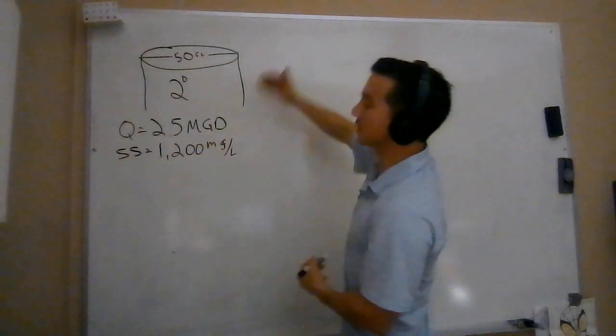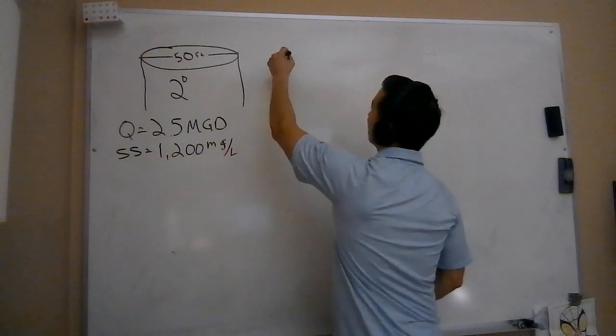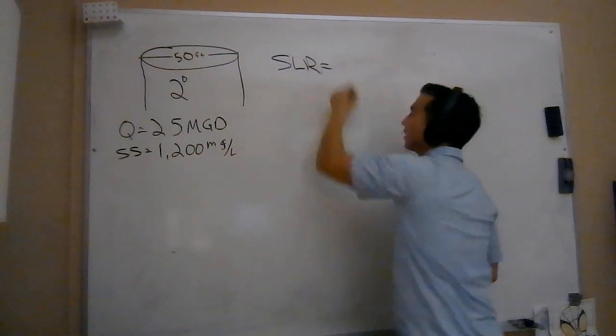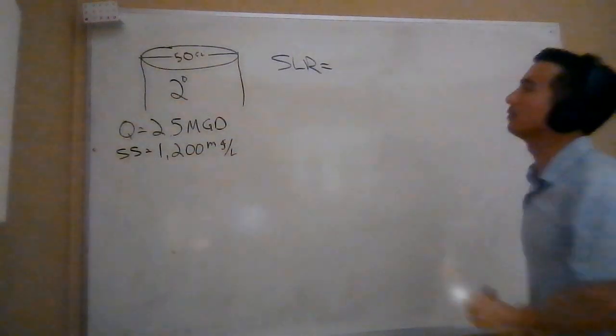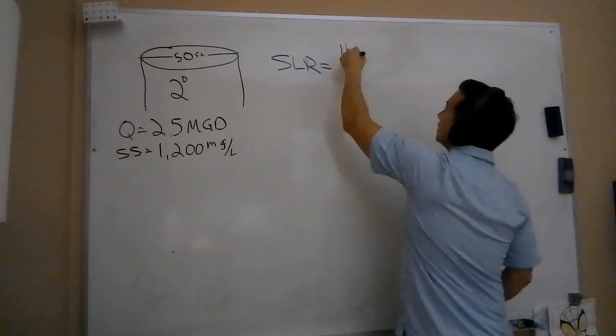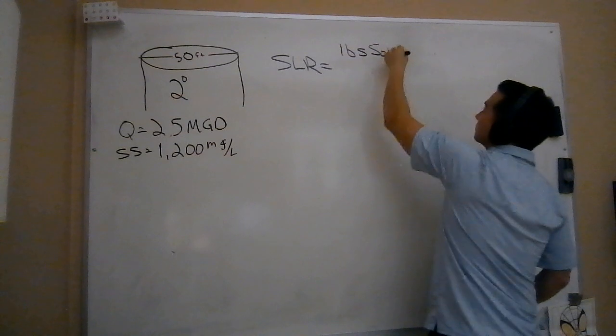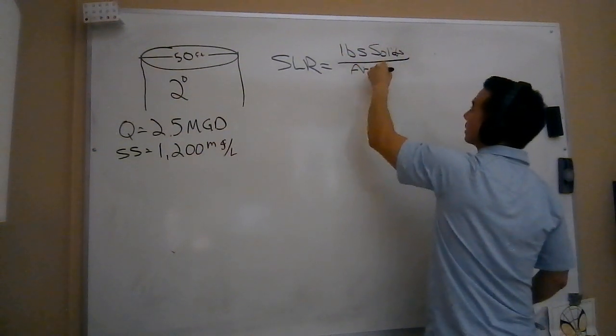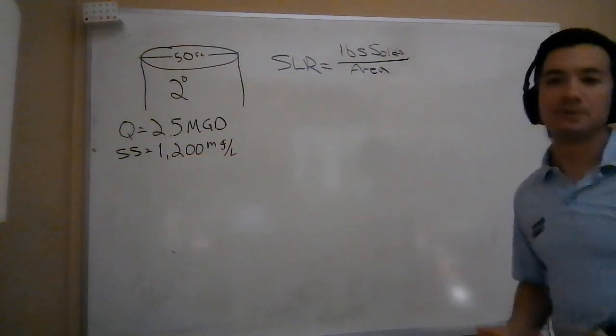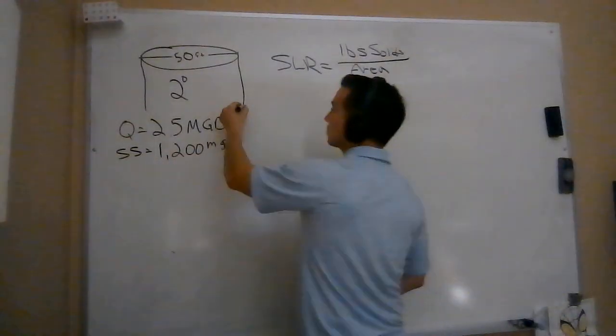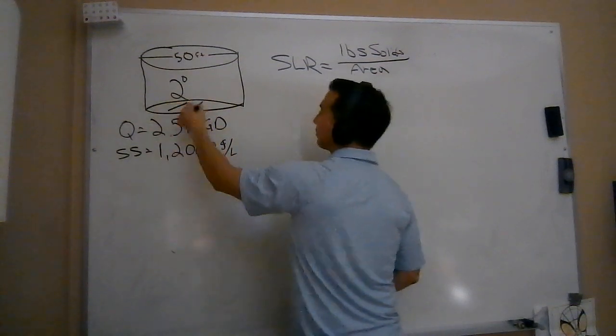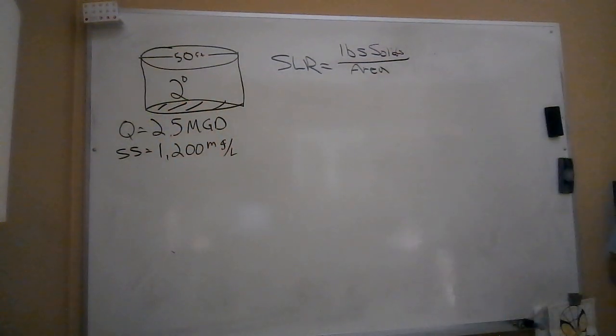My solids loading rate, or SLR - you've got to go to your wastewater formula sheet. That is my pounds of solids divided by the area of my clarifier, right? The area available to settle those solids out. If you picture the bottom of this clarifier, that's what we're dividing by - we're dividing by this area right here.